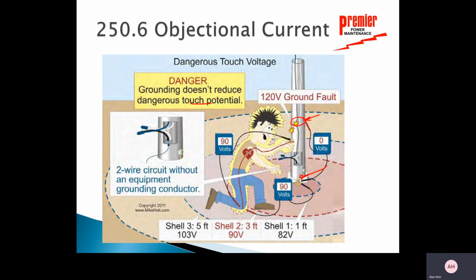So Mr. J right there, he feels pretty good because he's checked it for 0 volts. But look where his knee is. His knee's right here. That ground path has to provide current flowing back to the source. And so there's going to be some voltage drop between this location and where his knee is. Looks in this case, it's, for example, 90 volts, which means there's 90 volts from here to his knee, okay?